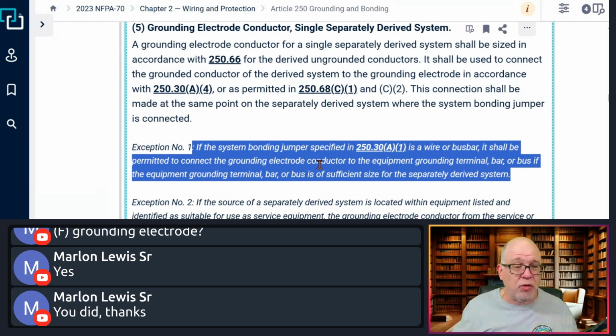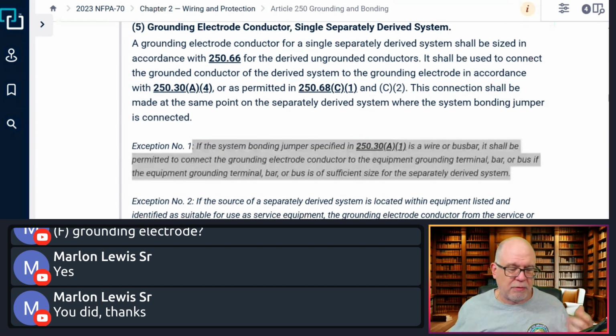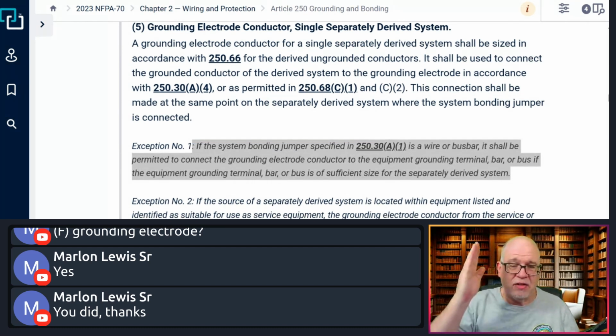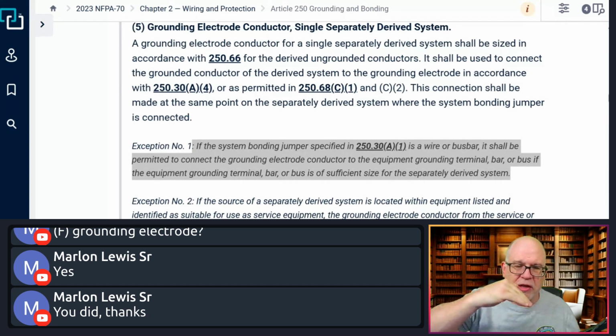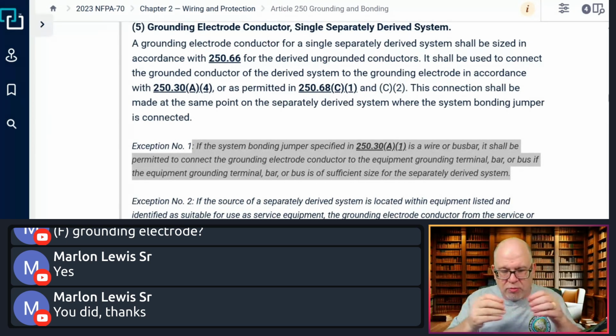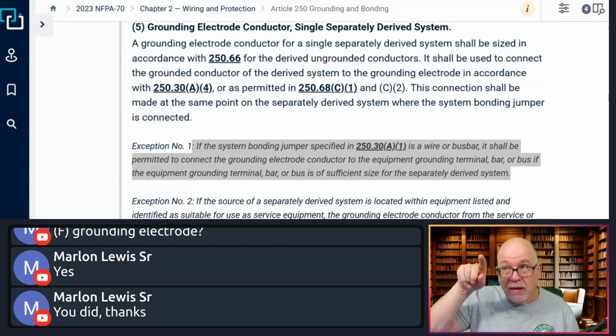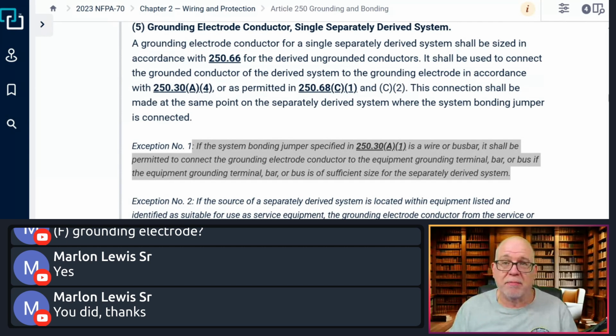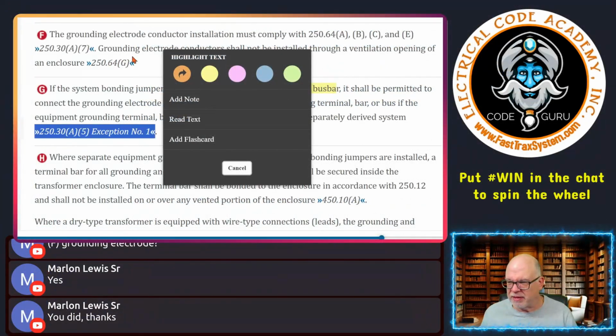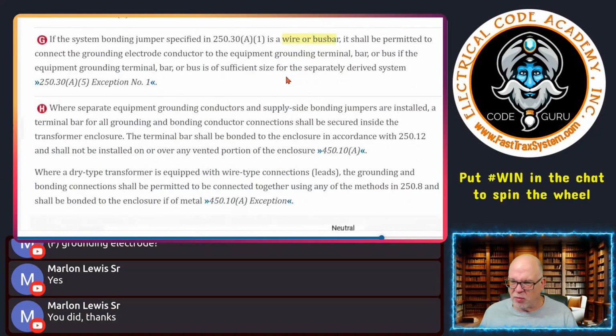But this does give you the ability to do exactly what Marlon's saying: not taking it to the XO, but taking it over to the equipment terminal bus. That's why they usually give you a bus with multiple set screws on it, because you can do that, provided your system bonding jumper is a wire or bus bar and it's sized properly. For us, me and you, we'll assume you did size it properly. So that's what that exception means with the wire or bus.